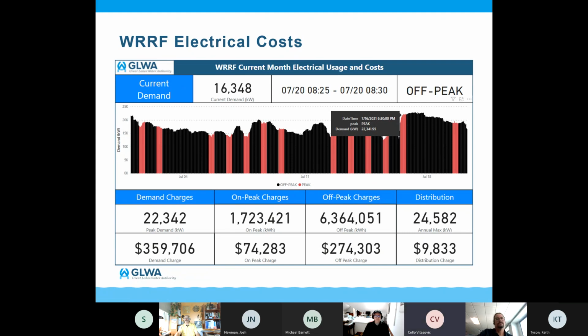What is the demand charge? What's the increment for the peak demand? Is it like a rolling 15-minute? It's the half hour. Every half hour, and it's just the kilowatts for that half hour. Yep. Ours is a little more. Ours is peak 15 minutes in every 5 minutes.